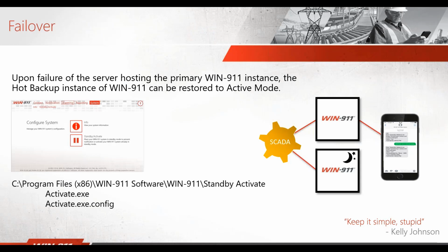Whenever you have a failure of the server hosting the first Win911, the backup Win911 can be restored into active mode. The way you would do that is with some executables that we include with Win911, which you can find in the folder location at the bottom of the slide. There's an activate executable, a standby executable, and another executable that you can use to query which state the dispatcher is in. Now, is that folder always going to be available in the C drive, or can it be found somewhere else? No, when you install Win911, it will always be there. You can take that folder and run it from anywhere on the computer, but that's where we initially install it. Excellent, thanks.